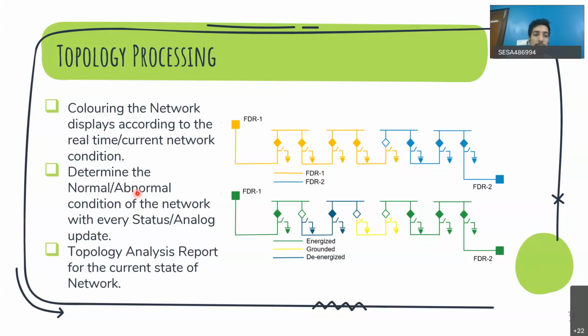Similarly, you determine normal and abnormal conditions of the network with every status or analog value change. The same network can be colored based on energization: green means energized, blue means de-energized, and yellow means grounded. So this part of the feeder is energized, this part is also energized, and even though they're fed by different feeders, since both are energized they're shown in green. This section in between is de-energized, not fed from either side, so it's shown in blue. This small section in between is grounded, with both switches closed and isolated, so it's shown in yellow. This way, at first glance, operators understand which part of the network is healthy, de-energized, grounded, or meshed.